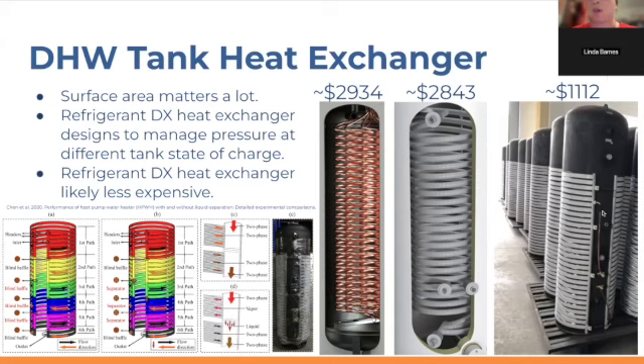And one of the challenges to solve is, okay, if I take back-to-back baths and drain the water heater tank, then I have cold water near the top of the tank. So if I put the hot refrigerant gas at the top, it will quickly be absorbed into the cold water at the top of the tank and therefore condense from a vapor into a liquid. But what happens if I only take a short shower and only have like 10 gallons of cold water at the bottom I need to reheat? Well, if you put the refrigerant at the top and it still needs to travel through all those top paths to make it all the way to the bottom, then it takes a long time. Then there's a bottleneck in the refrigerant flow to the bottom, and you get very poor heating performance at the bottom of the tank if you only have 10 gallons of cold water there.